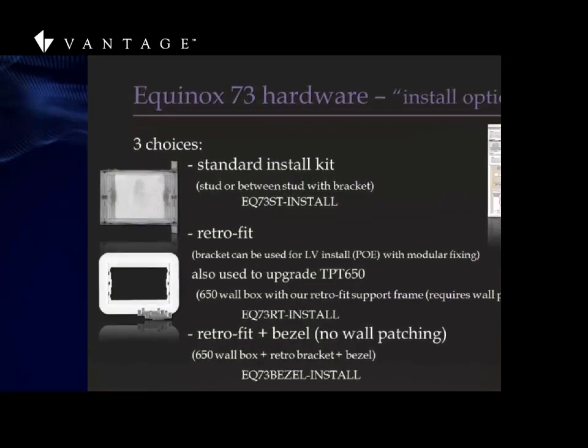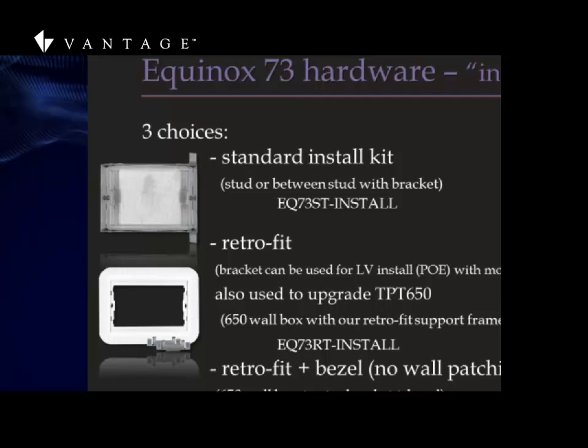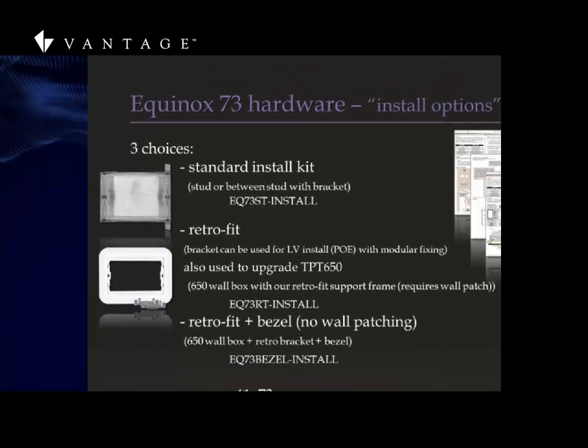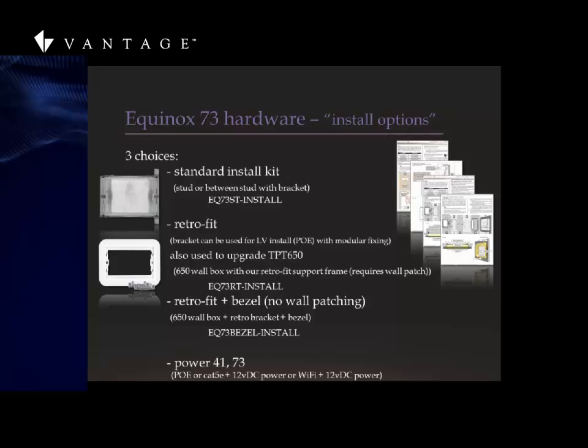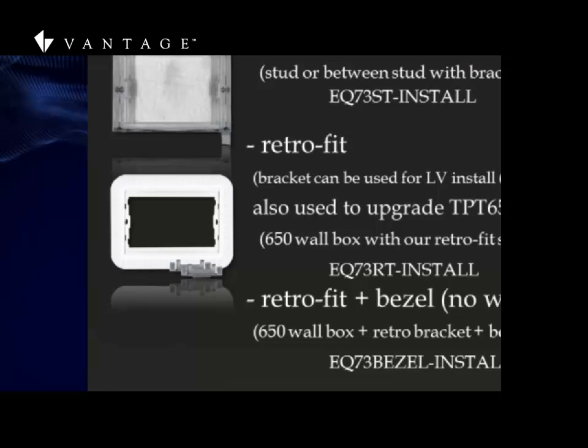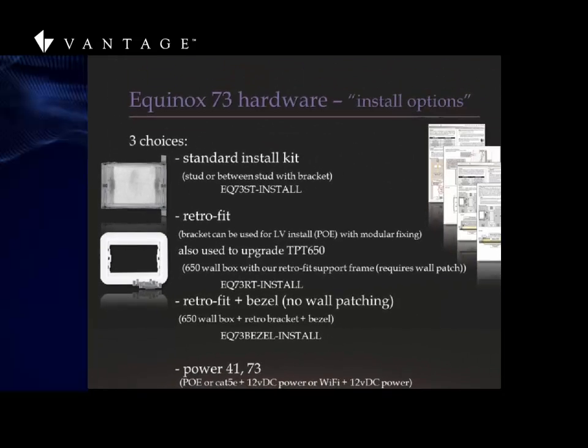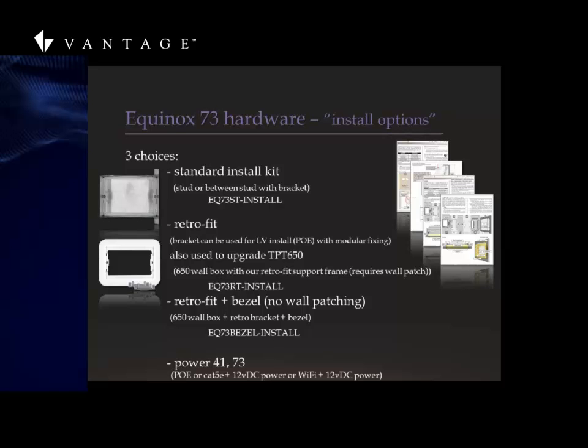Let's take a look at 73 hardware installation. You've got your standard install kit for pre-rough-in installations where you can mount this directly onto the stud. You also have a retrofit ring, which you can cut into the sheetrock and clamp onto it, with a wider bezel around the edge riveted with holes to allow sheetrock patching and finishing. The power for the 41 and 73 Ethernet-based devices can be either the 12-volt power supply from the 650, or you can use a power injector — PoE over Ethernet.